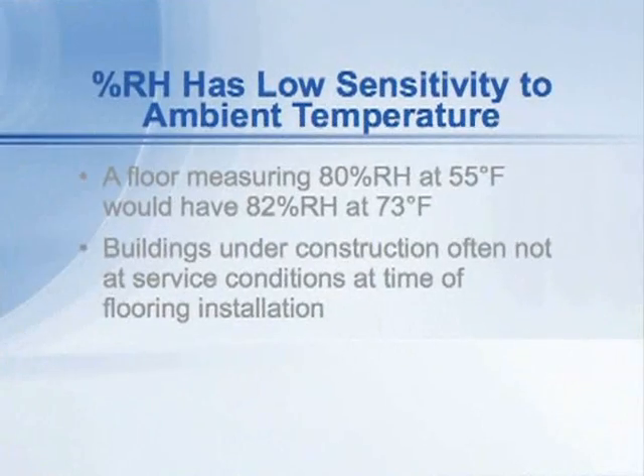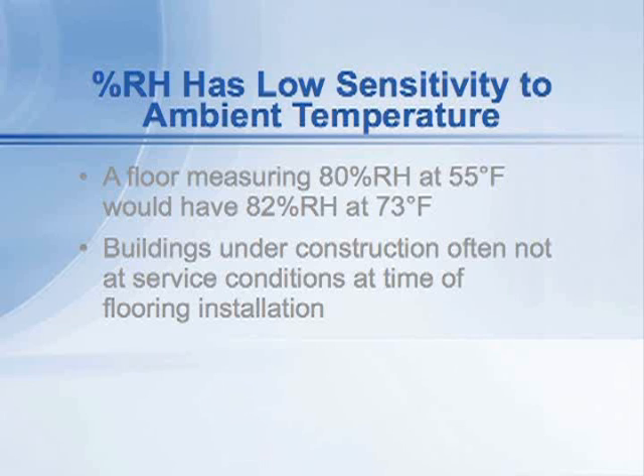As an example on this next slide, I can show you some numbers based on some of this preliminary work. For example, if you go out to a building at 55 degrees because the heat's not on yet and we measured, let's say, 80 percent relative humidity in the floor, it turns out that when that floor gets up to 73 degrees at service conditions, the humidity in the floor will only go up two points — up to 82 percent. So potentially we'll be able to go out and make these measurements before we're at service conditions, which is going to be much more useful than other test methods.